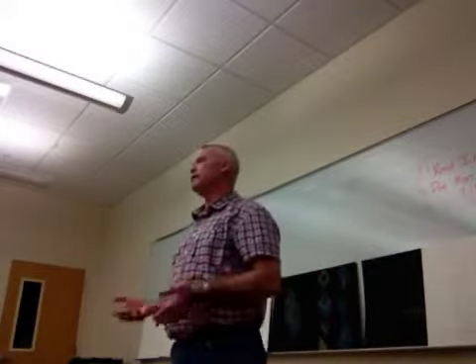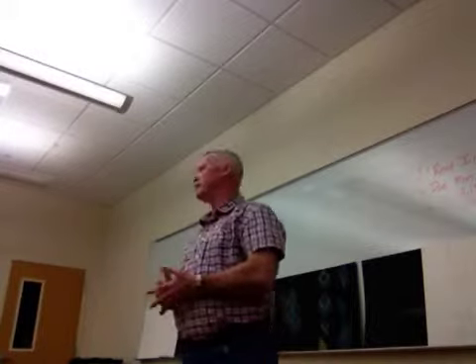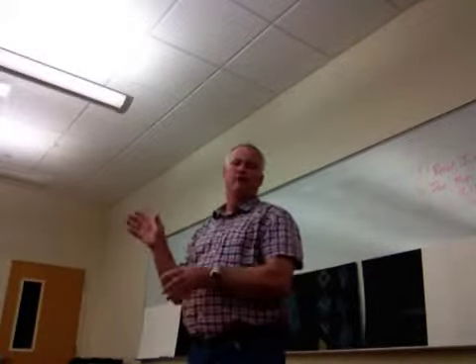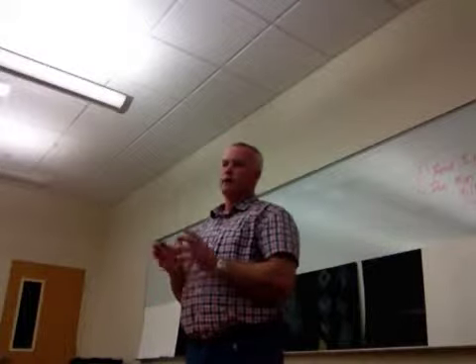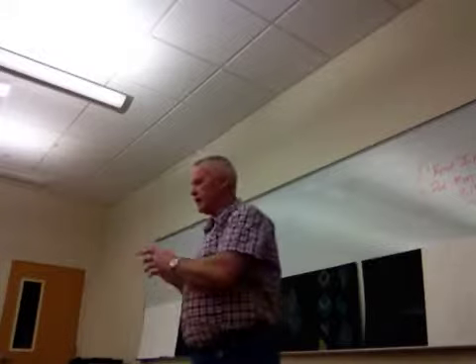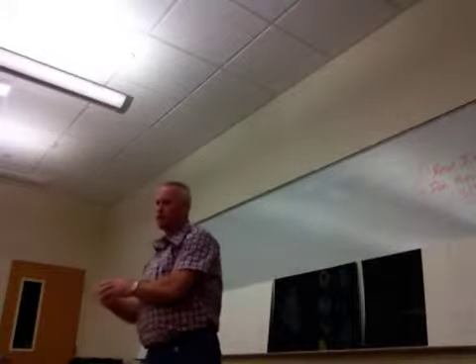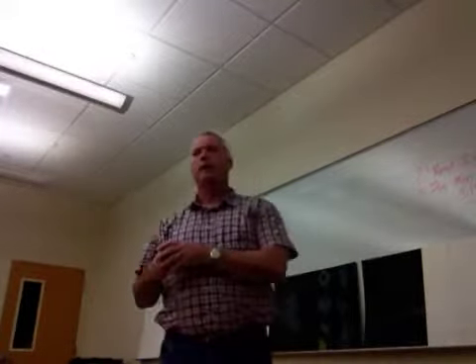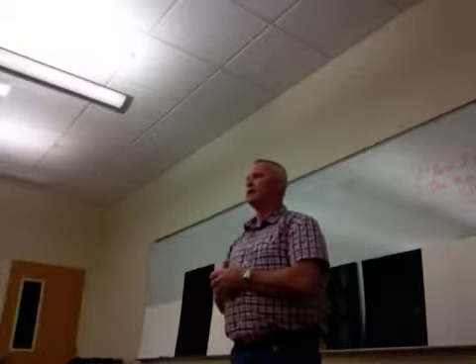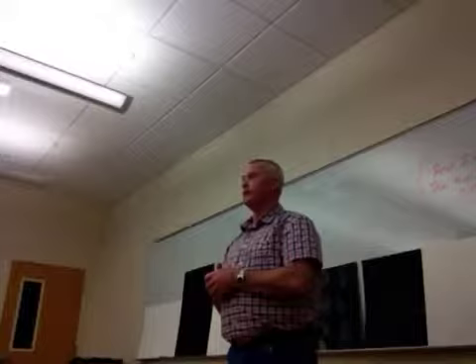So the bigger the building, the bigger the service entrance, the bigger the gear. You don't want to think after the fact, well, where are we going to put our electric room? Another consideration is on your site plan, where's the power coming into the building? You try and get over on that end of the building and minimize your copper runs and the cost of your feeders. Some of these copper lines are like $10 a linear foot.